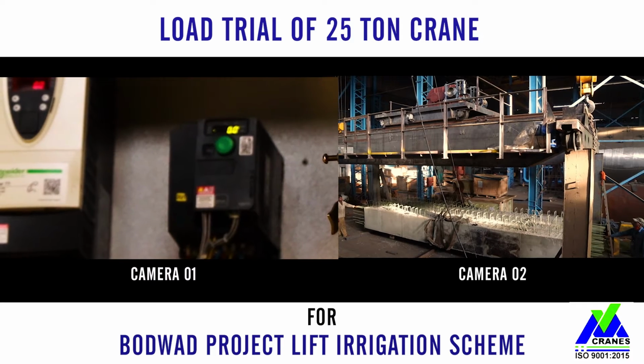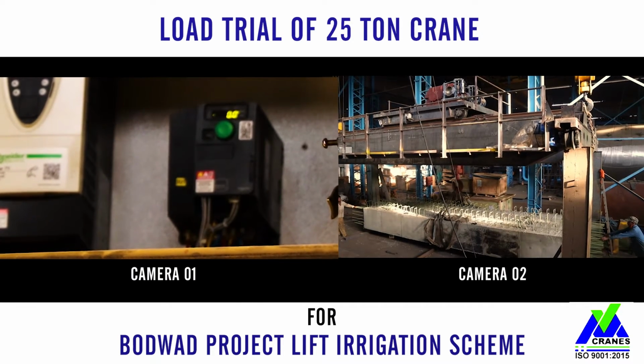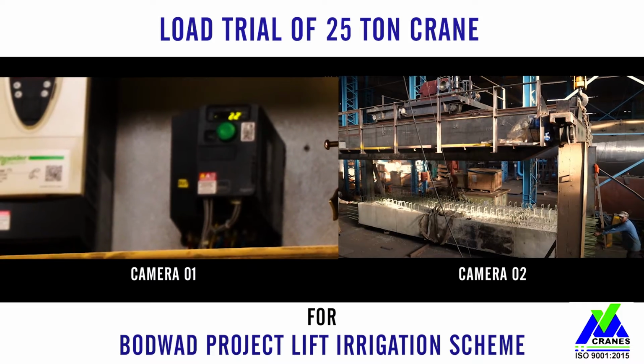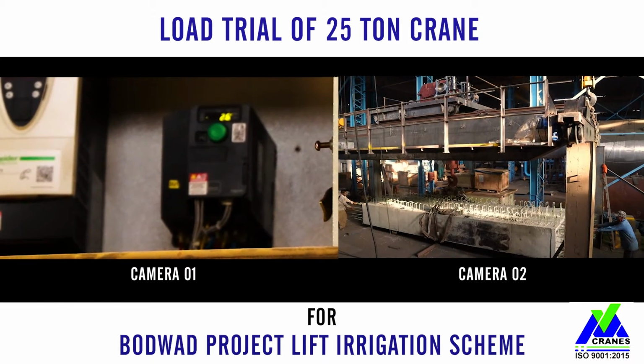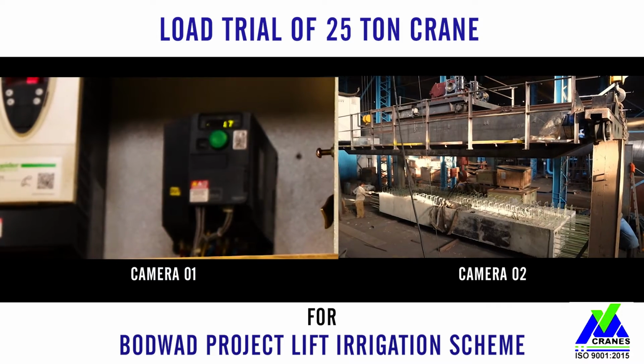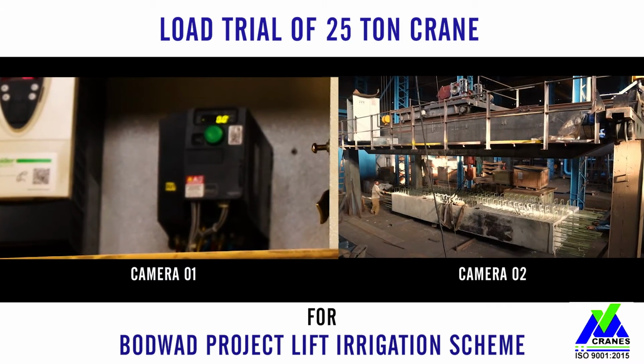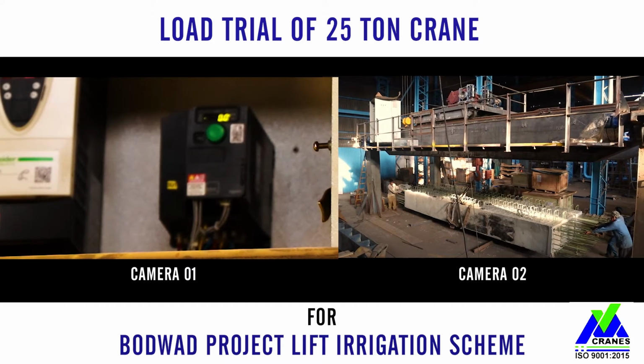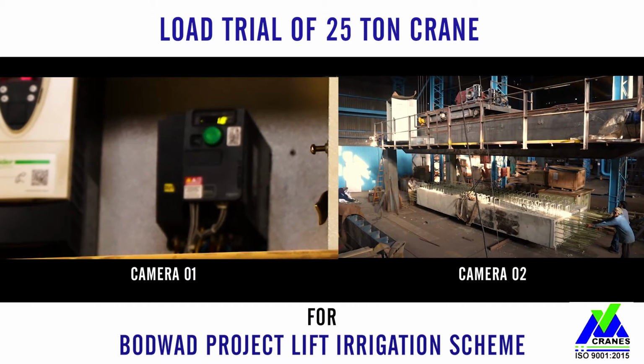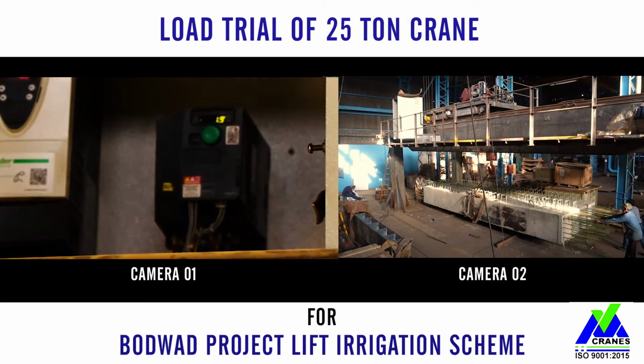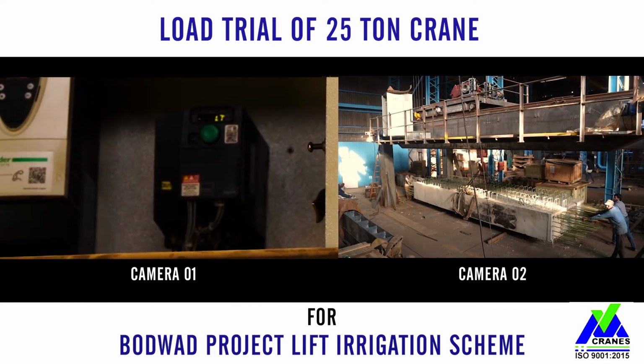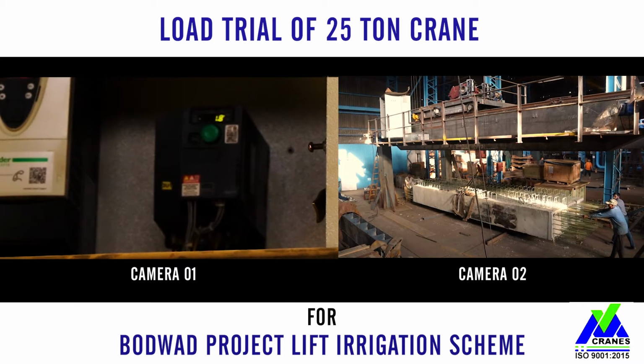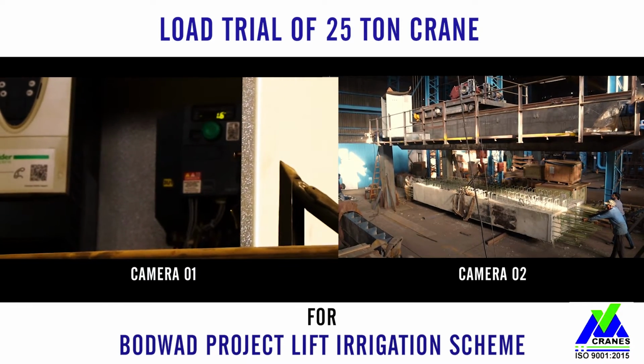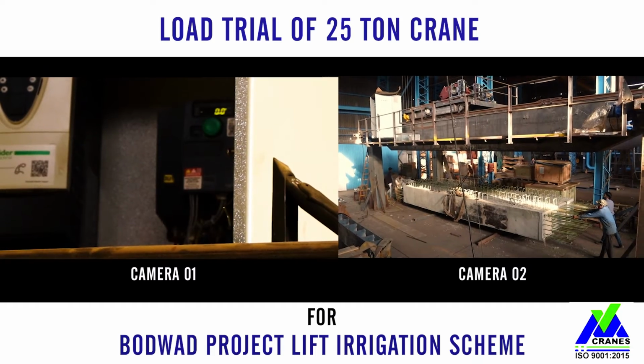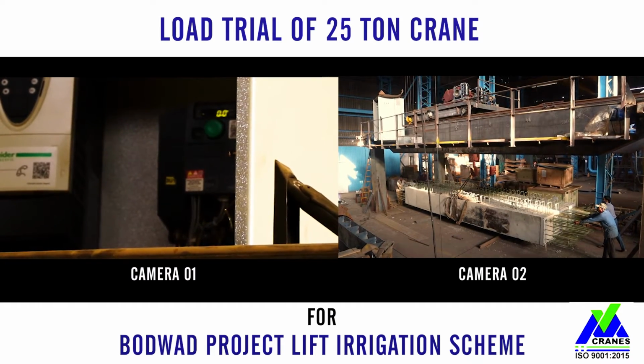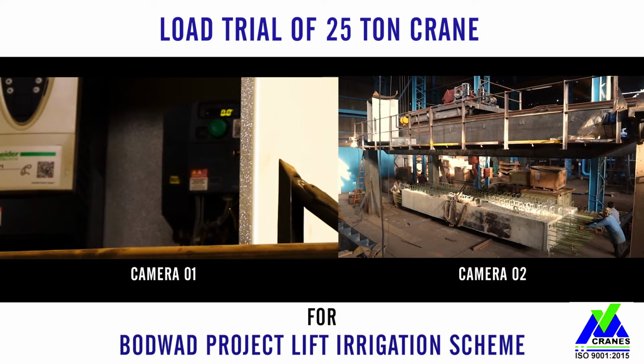Now the rated load has been lifted and the cross travel movement, we are driving the cross travel motion with the rated load of 27,720 kg. You can witness the current on the VFD display. For the cross travel, two motors are connected. Hence, the current observed for both the motors in forward direction is 1.7 amps and 1.9 amps in the reverse direction.